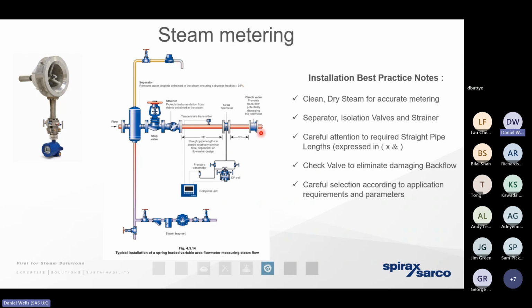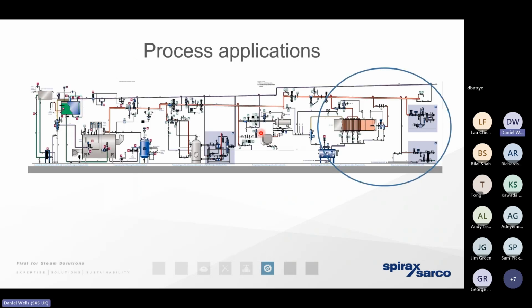valve to protect backflow. We need to have the correct linear run of pipework upstream and downstream of the meter so that we're not in a position where we've got turbulent flow or an inaccuracy with the reading. So we need to think about a meter as a station rather than a standalone device. So it's only when we've ensured that we've followed that best practice with generating the steam and distributing the steam that we can say that the steam is going to arrive at the heat exchanger at the condition that we expect. Remember, we want that steam to exist as close to or on that dry saturated steam line.